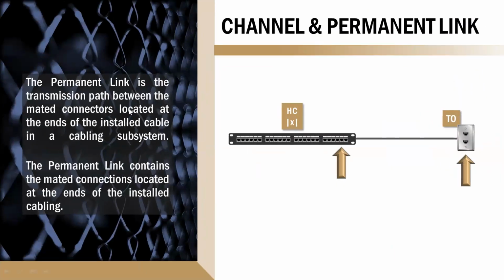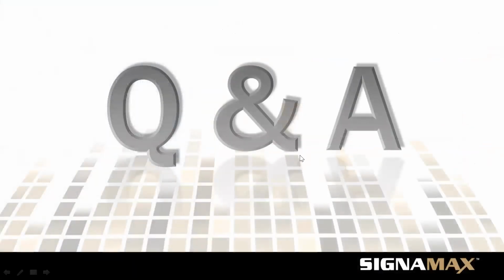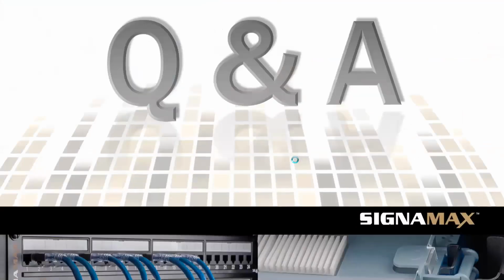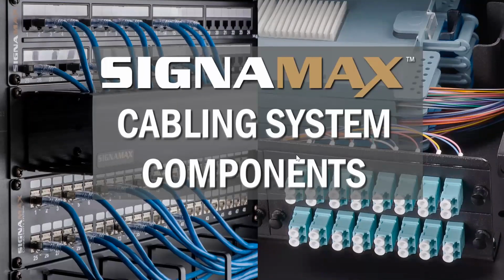The permanent link is the transmission path between the mated connectors located at the ends of the installed cable and the cabling subsystem. The permanent link contains the mated connection located at the ends of the installed cabling. So this is what you're testing, and the standards are 10% tighter on permanent link than they are on channel. Any questions about that? Good. You'll find that you can pass channel sometimes, but you may be failing permanent link.